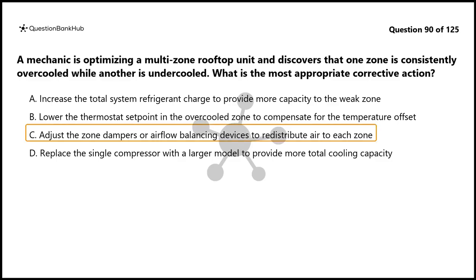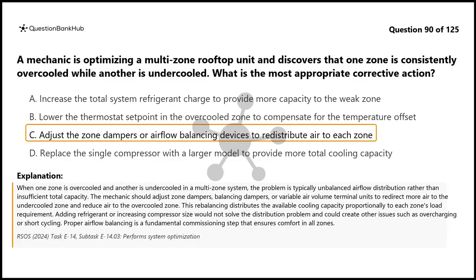The correct answer is C. When one zone is overcooled and another is undercooled in a multi-zone system, the problem is typically unbalanced airflow distribution rather than insufficient total capacity. The mechanic should adjust zone dampers, balancing dampers, or variable air volume terminal units to redirect more air to the undercooled zone and reduce air to the overcooled zone.